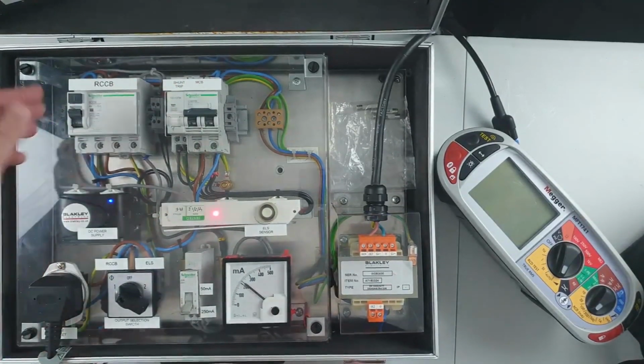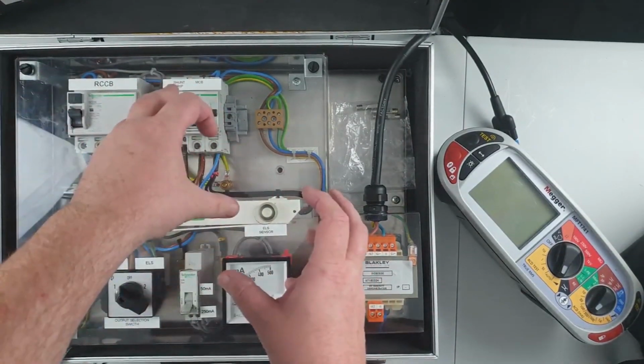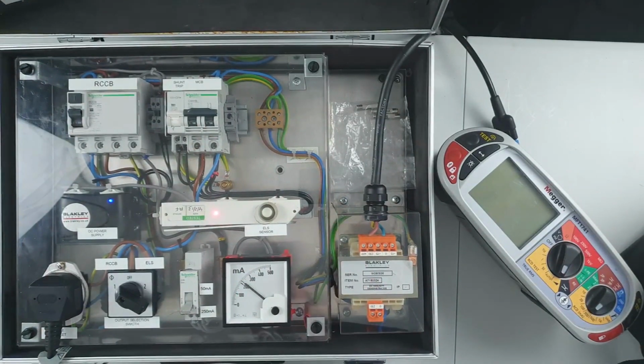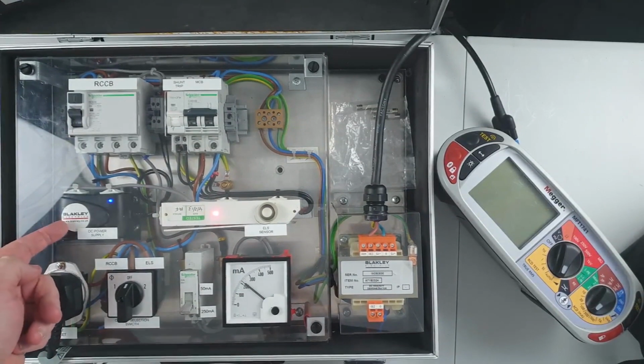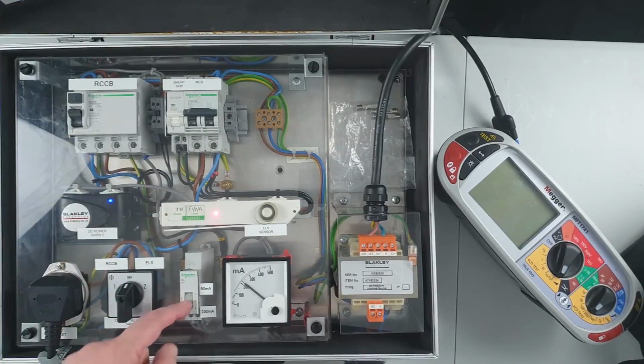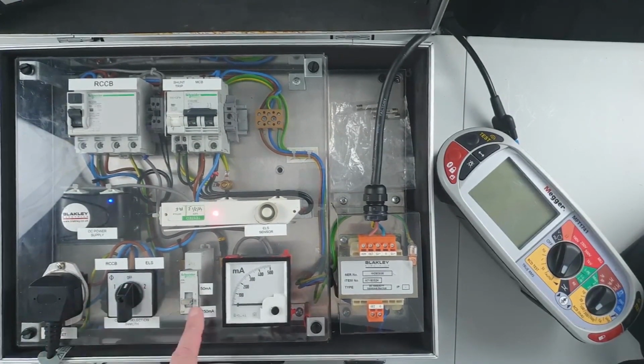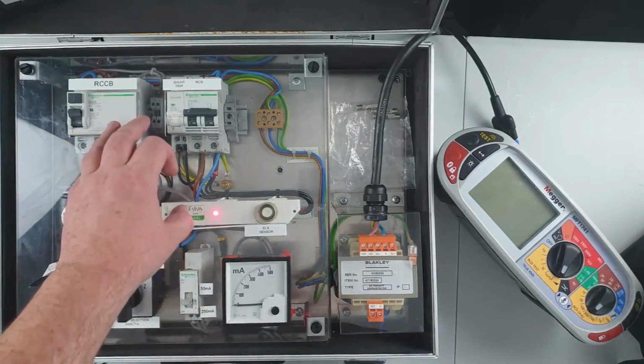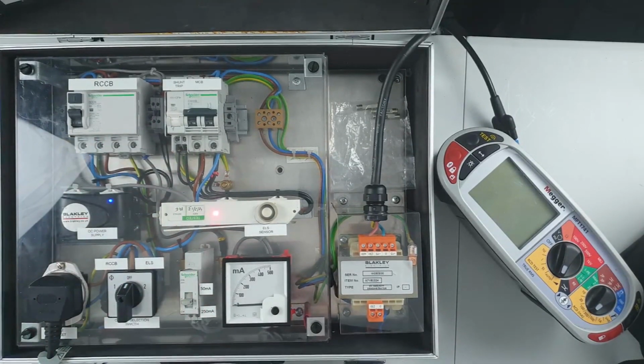Basically, we have an RCCB here or an RCBO here. And this switch just selects between one or the other. We have a DC supply, and that goes through to this switch here, which can push through a 50 milliamp leakage into this system or a 250 milliamp leakage.